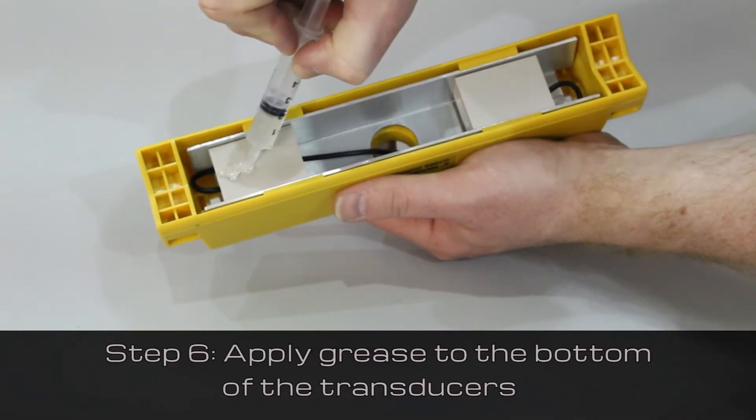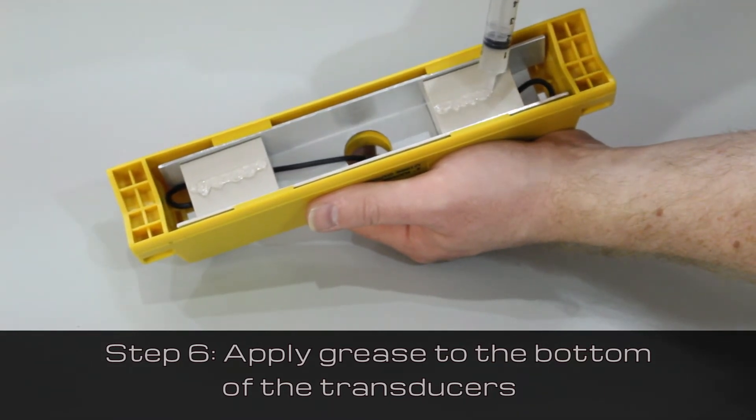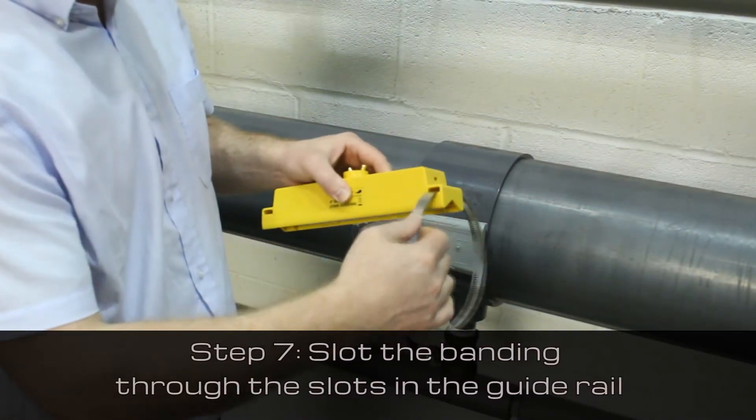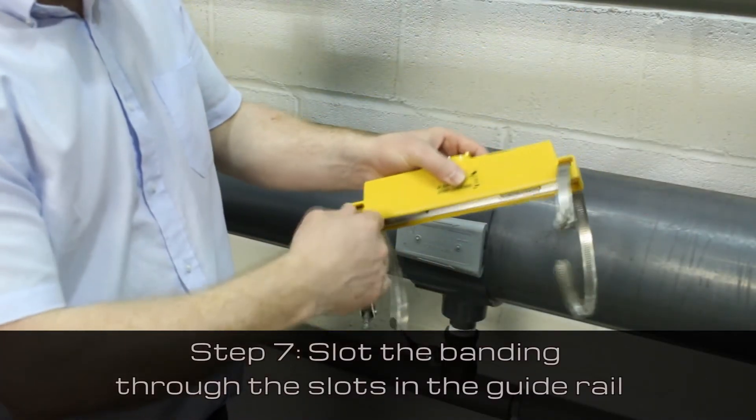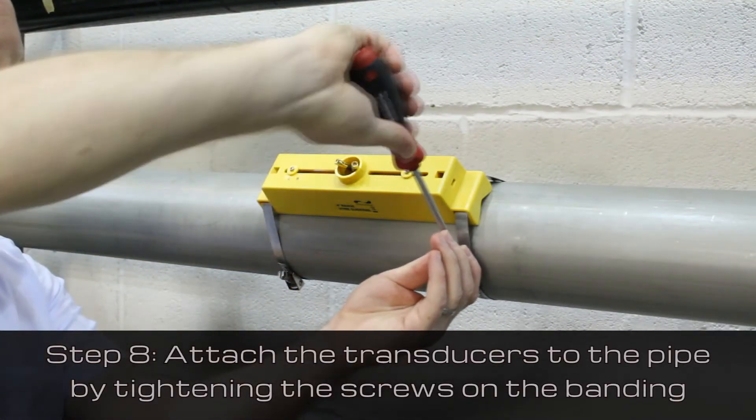Next, apply grease to the bottom of the transducers. Then, slot the provided banding through the slots in the guide rail. Attach the transducers to the pipe by tightening the screws on the banding.